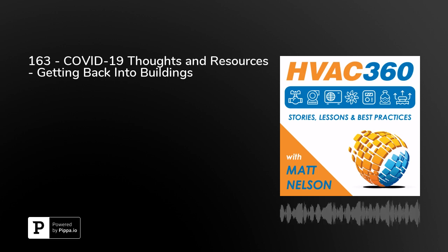But there are 3 ways you can use UVC. One is in upper-room air systems, interrupting the transmission of airborne infectious diseases in high-traffic and communal areas. Because the HVAC system is generally good at churning the air, a portion of the air, especially coming out of the diffuser, will hug the ceiling, go down the walls, and then come back up.